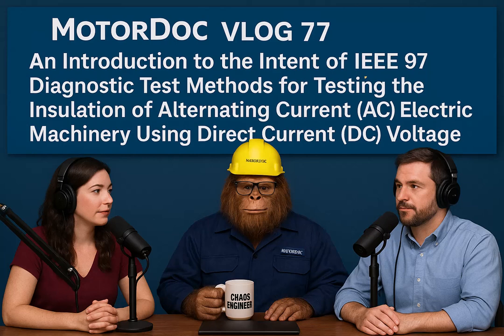Okay, then what? Then comes the absorption current, sometimes called dielectric relaxation current. And that one sticks around longer. Yeah, it decays much slower, over seconds, minutes, sometimes even longer, really depends on the material. This current is related to the polarization of the insulation material itself. Polarization, like molecules lining up. Kind of, yeah. How its molecular structure aligns under that electric field. Its characteristics are tied to the material type, its condition, dimensions, temperature. Got it. And the last part.